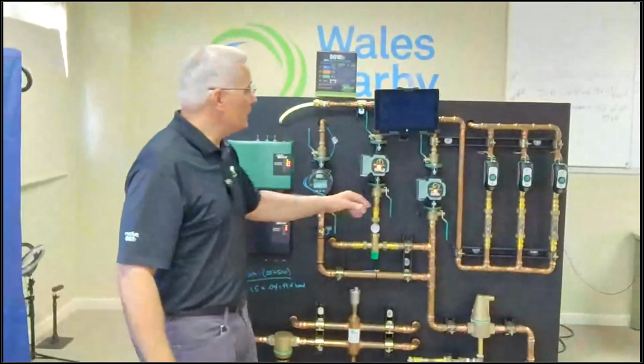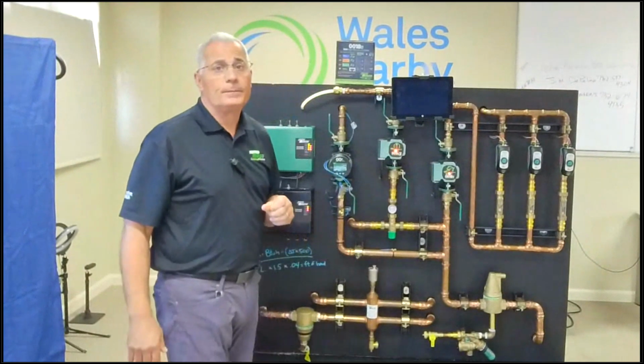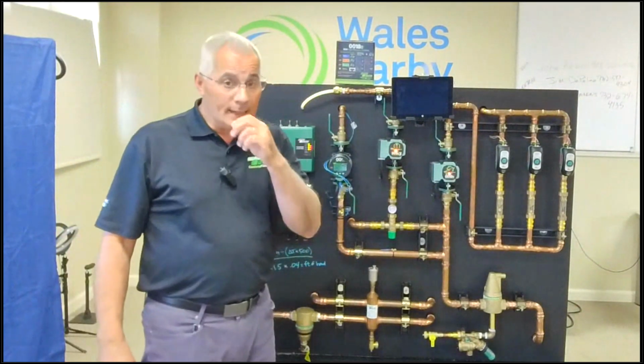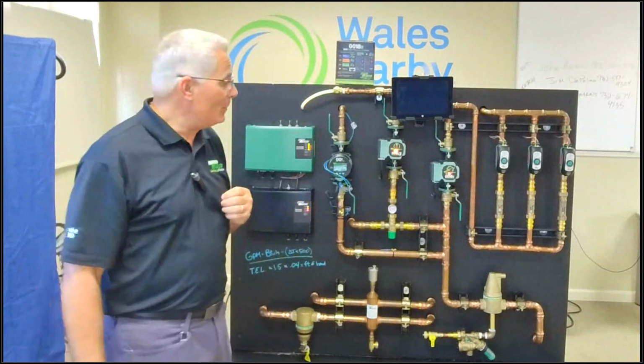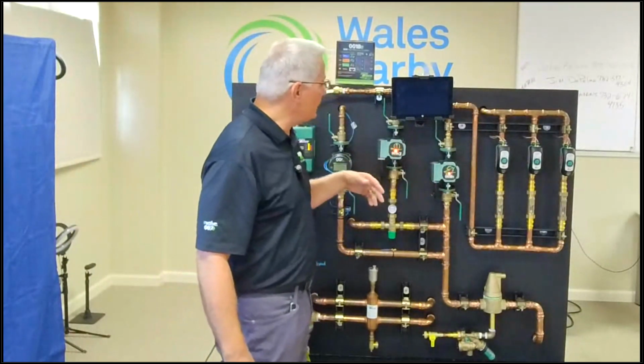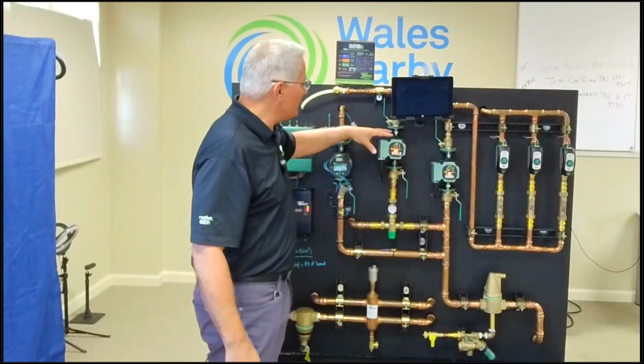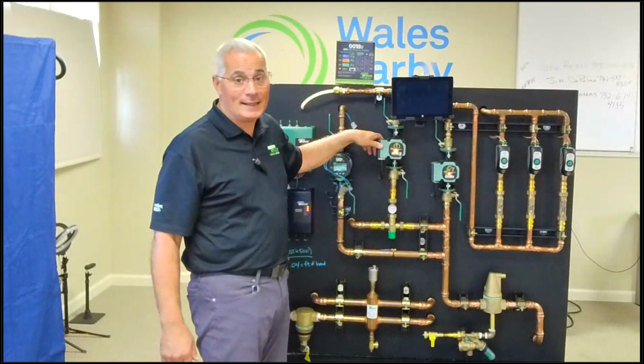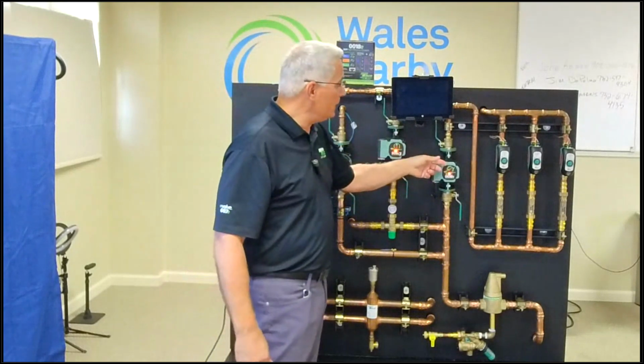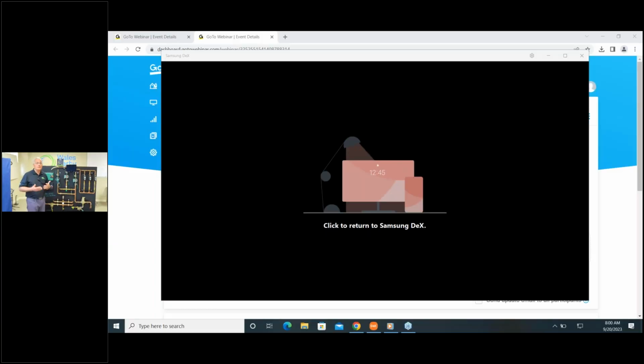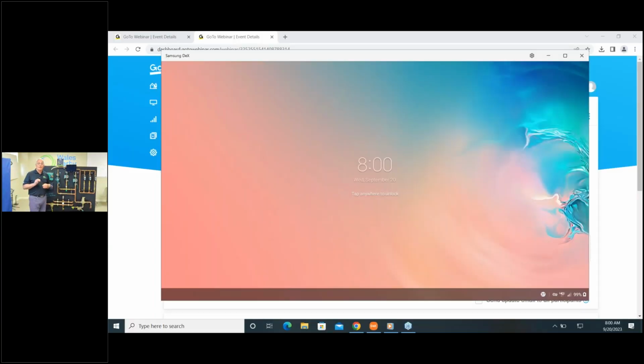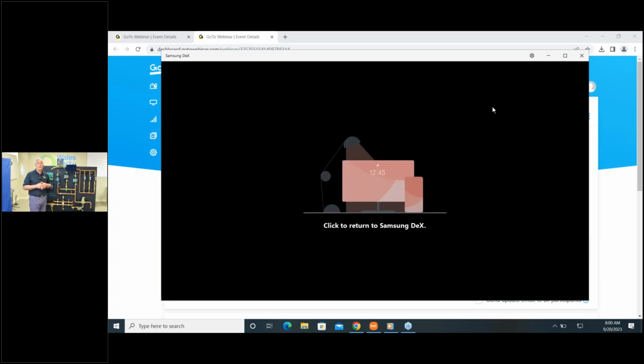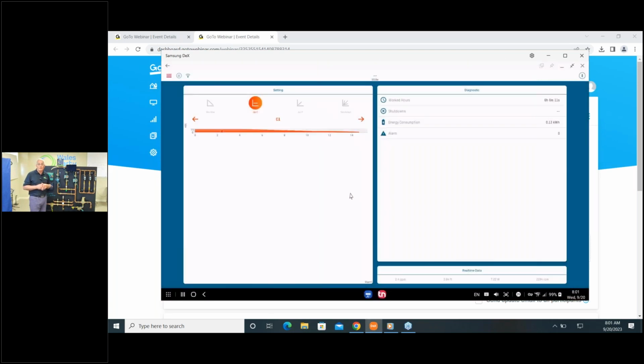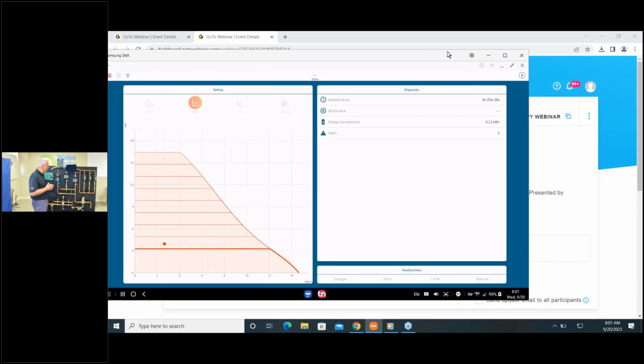All right, Chris, if we could enable the screen to show off this 0018E. So what we're going to do now is take you to the Bluetooth capabilities of this 0018E. The 0018E is a souped up version of this 0015E3, if you want to think about it this way. And it gives me the ability to go through different modes. I could set this pump to do different things: constant pressure, a fixed speed, or if I'm using a system that's got thermostatic radiator valves, the Danfoss valves, I can set it up for a constant circulation system here.